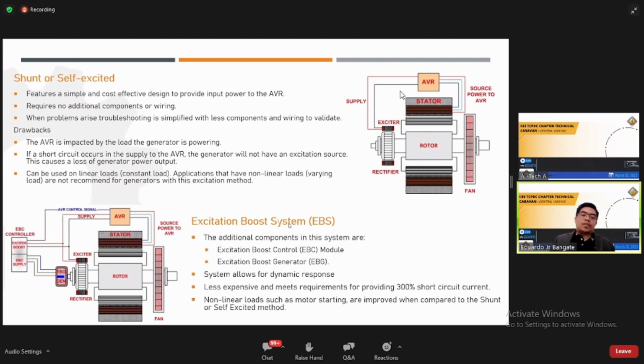Okay, so the second one is the excitation boost system, or the EBS. You can see the diagram of an EBS type excitation system on the left side. There are additional components in this system, like the excitation boost control, or EBC, module, and the excitation boost generator. The system allows for dynamic response, is less expensive, and meets requirements for providing 300% short circuit current. So this is better than the shunt or self-excited because it has the capability of providing 300% short circuit current into the generator, just in case there is a requirement for that. Non-linear loads such as motor starting are improved when compared to the shunt or self-excited method. So it is better than the previous one.